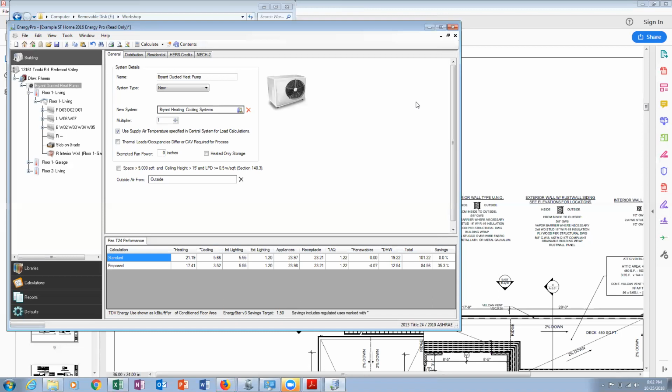So if you were doing certain types of like gypsum board, plywood, if you did like special components to that and you wanted to get energy credits for it, CBECC-RES would allow you to kind of play with those and it would show the energy benefit of changing things on your wall layers. Whereas in Energy Pro, the wall layers are really only a functionality for non-residential modeling. So even though it shows you layers in Energy Pro, you're not allowed to really change them.